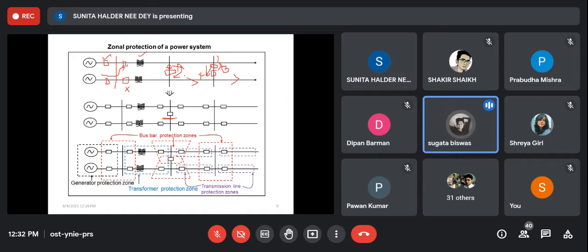Actually, ma'am, in the bottom picture there is no protection in the right hand bus bar. The rightmost bus bar, there is none. I have shown you different possibilities: one bus bar with sectionalization, another bus bar without sectionalization. Normally there should be sectionalization, but sometimes it may happen that it has less importance, so we may not give it, because if you want to provide every protection, cost is one issue.